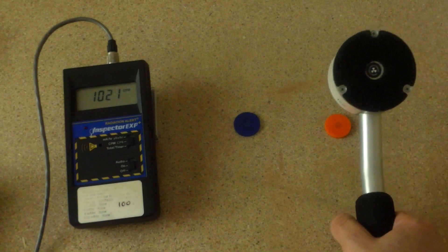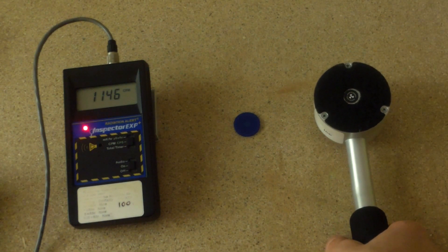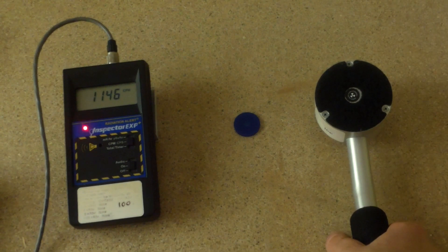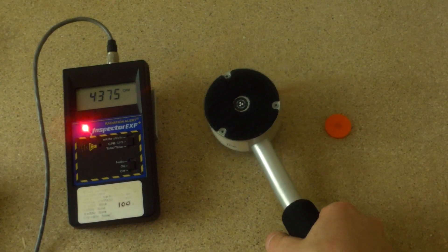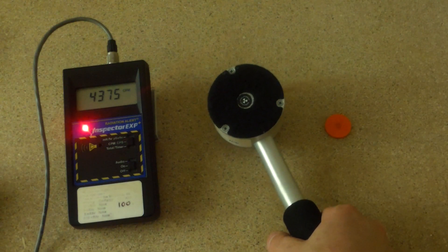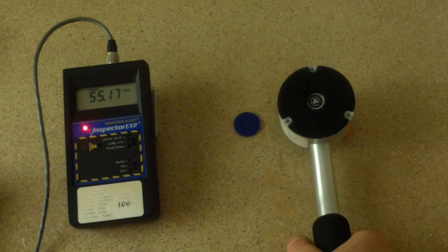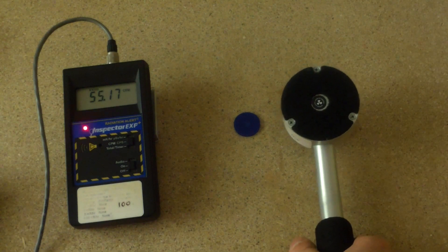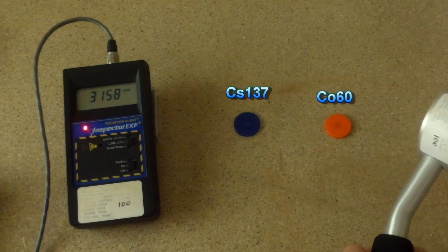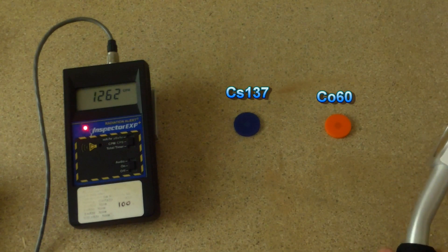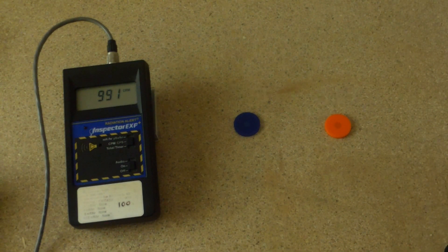Geiger counters are also not very good at telling the difference between two radionuclides. They can tell me that both of these samples are radioactive and give some indication of the type of radiation being detected, but they cannot tell me which one is cesium-137 and which one is cobalt-60. I would need a different piece of equipment to determine that.